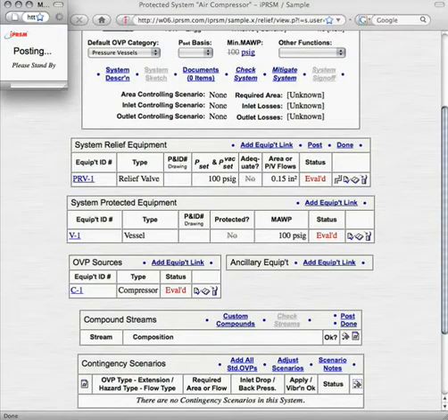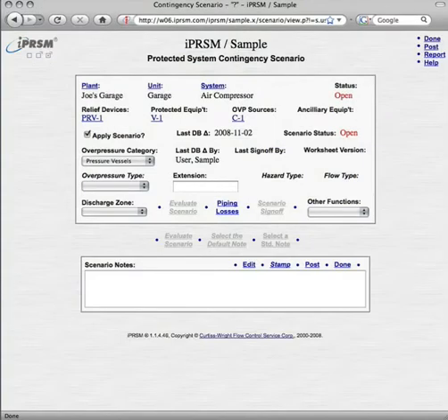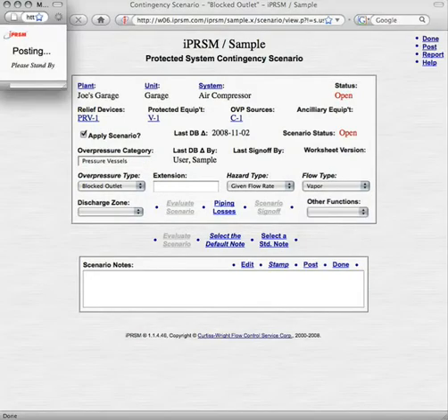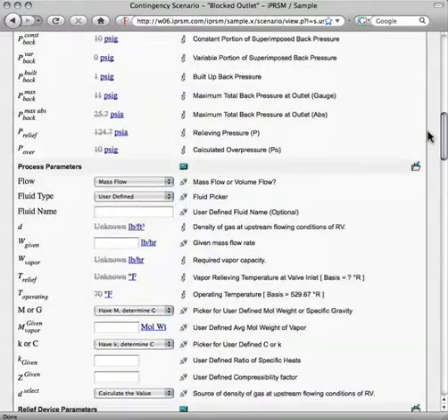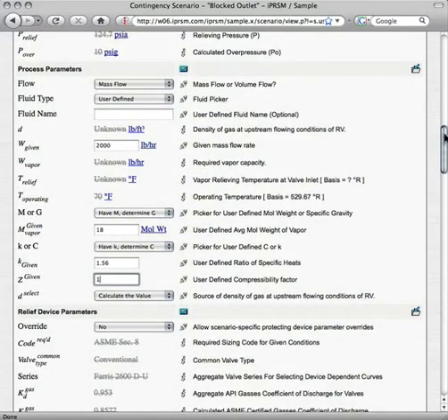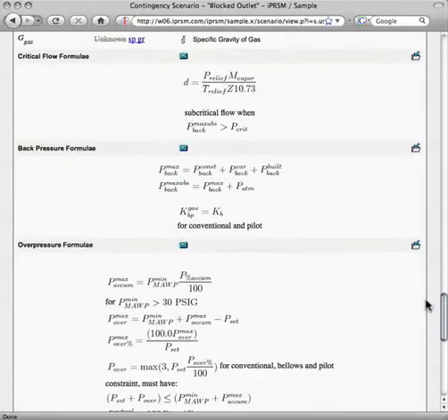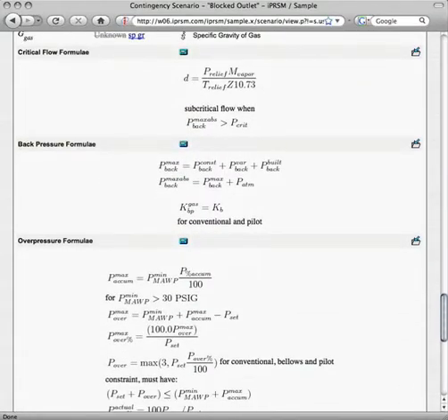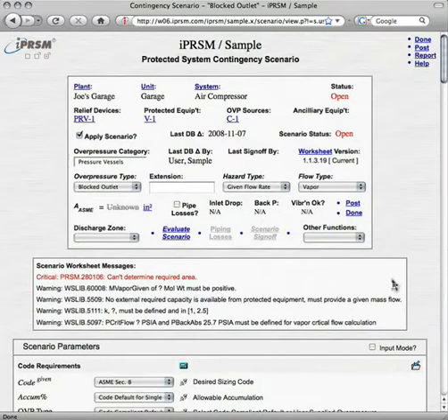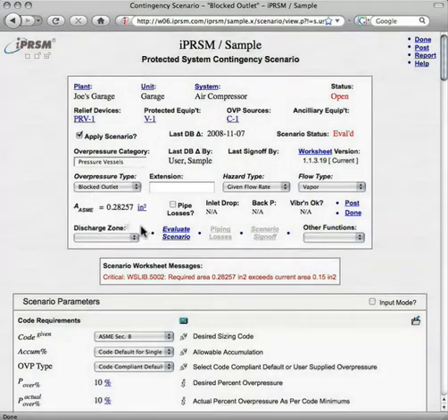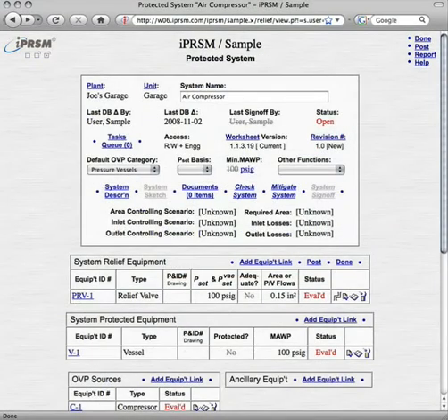Now we add a contingency scenario to our system. Recalling that the purpose of this exercise is to ensure that the valve we selected is adequate to relieve overpressure in the vessel if the compressor overruns, we specify the overpressure type, the hazard type, and the flow type for our contingency scenario. We'll skip over the details of entering the parameters, and note that here are some of the formulas that iPRSM uses to ensure compliance with engineering and regulatory standards. Now we evaluate the scenario to determine the required relief area. Returning to the protected system, we check the system to ensure that the relief device is adequate for the calculated relief area.